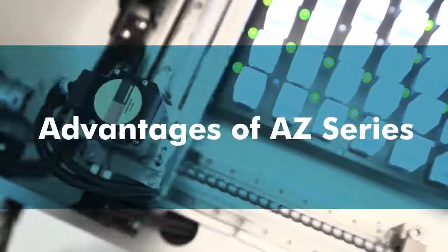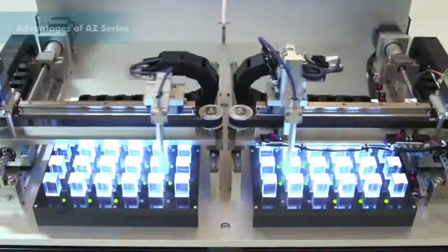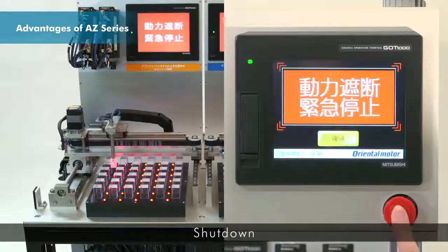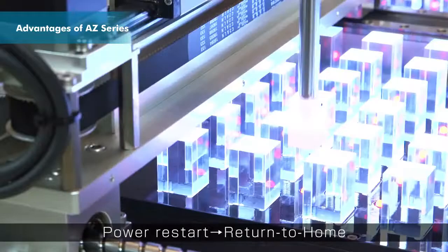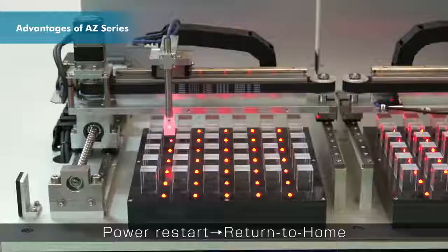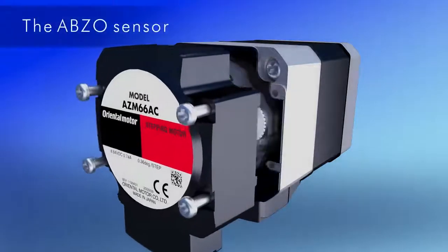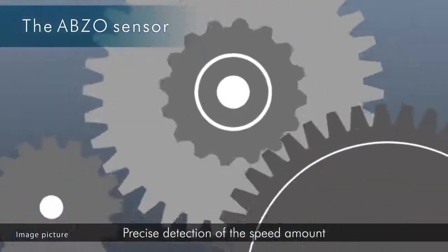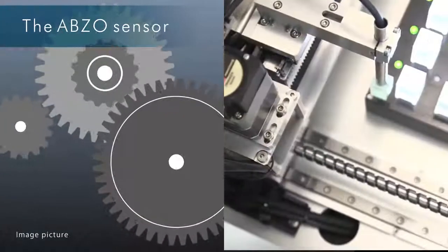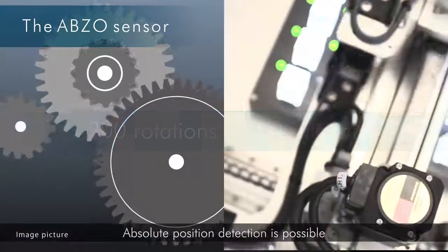Let's look at the advantages of the AZ Series Absolute Sensor. When the power supply is shut down during positioning operation, the AZ Series ABZO sensor preserves the position precisely. The ABZO sensor uses multiple gears to detect the amount of the motor's rotation, enabling absolute position detection within plus or minus 900 rotations of the motor shaft from the home position.